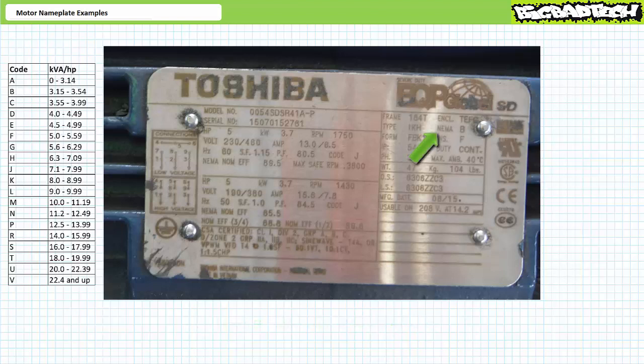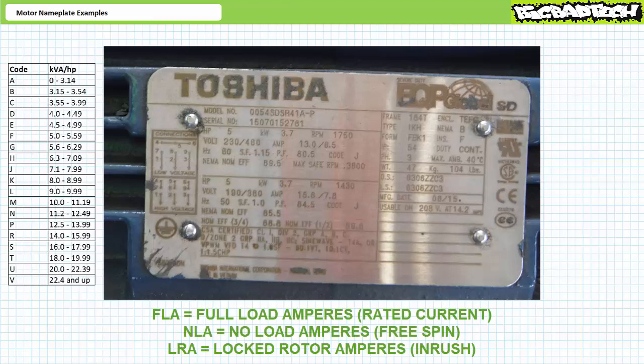The design entry might have taken you some work to find. This particular nameplate doesn't explicitly state 'design' but rather says 'NEMA,' meaning NEMA design — in this case B. Be aware of this type of variability. Motor manufacturers haven't adopted a standard template, so anything goes. The design entry might be called design, design code, NEMA, or NEMA design. The inrush code entry might be called kilovolt ampere per horsepower code, inrush code, or just 'code.' Current has acronyms: FLA means full load amperes (the rated current), NLA means no load amperes, and LRA means locked rotor amperes. Be flexible and smart enough to interpret whatever they throw at you.